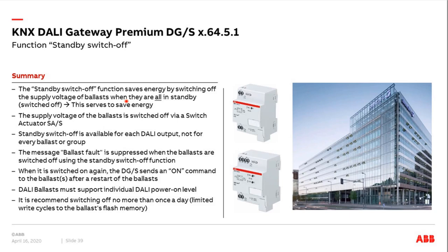Summary: with the standby switch-off function we can save energy by switching off the supply voltage of all ballasts via a switch actuator — or for higher loads, via an installation contactor. When the supply voltage is switched off, no ballast fault message is generated. This function is only possible when all ballasts on one DALI output are in standby mode, and the DALI ballasts must support the individual power-on level set to 'last value before failure'. Do not switch on and off too frequently, as instantaneous values are stored in flash memory, affecting ballast lifetime.